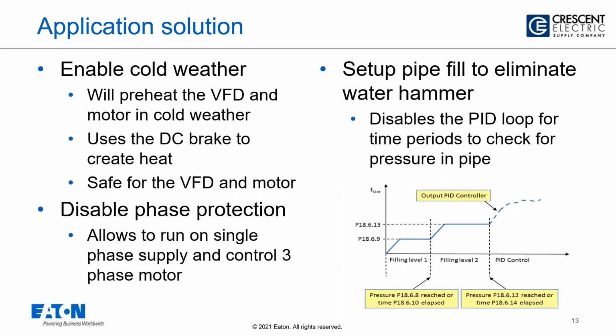And one of the things is, if you use that during the start when the pipes are not primed yet, it will try to run the pump at a full higher speed, leading to pump hammering. But there is a primer function available, so it disables the PID function for a particular duration and pre-fills the pipes at slower speeds for a certain duration, and then you can have 2-stage filling, just like shown in the graph at the bottom right. And then once the pipes are filled, bring in the PID control for your pressure regulation. That feature is built-in and easily configurable within the drive.